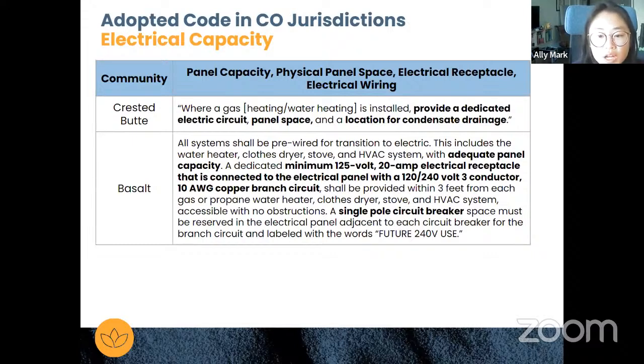Basalt has language requiring, for water heaters, clothes dryers, stoves, and HVAC systems, pre-wiring with adequate panel capacity, and a dedicated minimum 125 volt, 20 amp electrical receptacle connected to the electrical panel, with a 120 or 240 volt, 3 conductor, 10 AWG copper branch circuit provided within 3 feet of each gas or propane water heater, accessible with no obstructions. A single pole circuit breaker space must be reserved in the electrical panel adjacent to each circuit breaker for the branch circuit, labeled 'future 240 volt use.' That captures the spectrum from general to very specific.